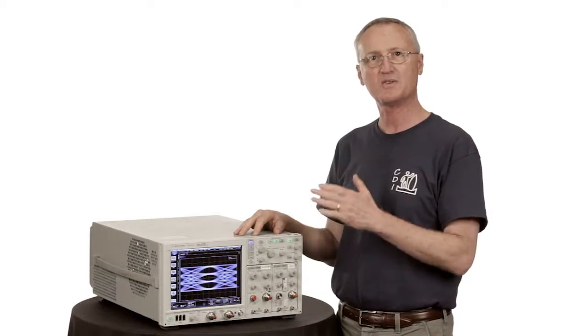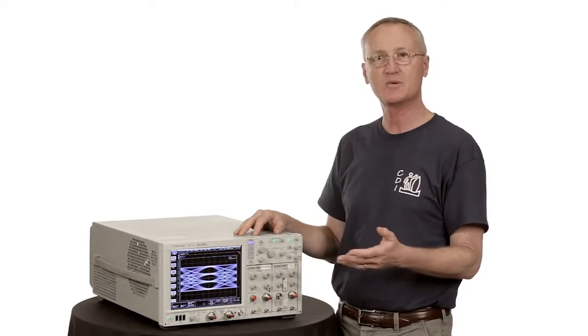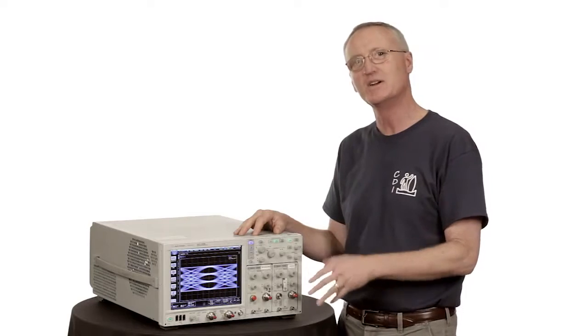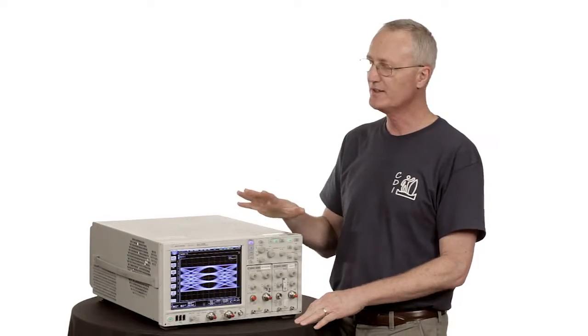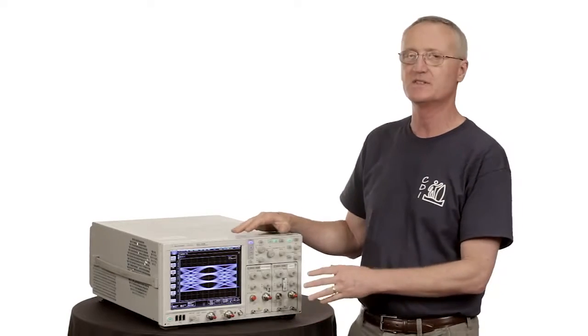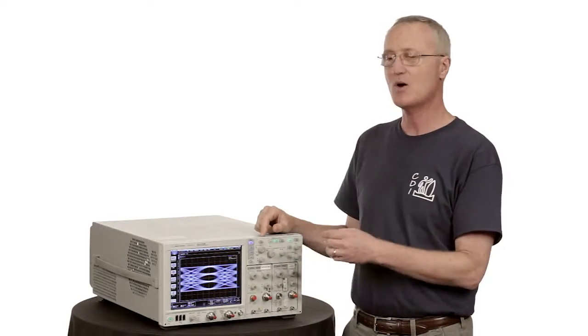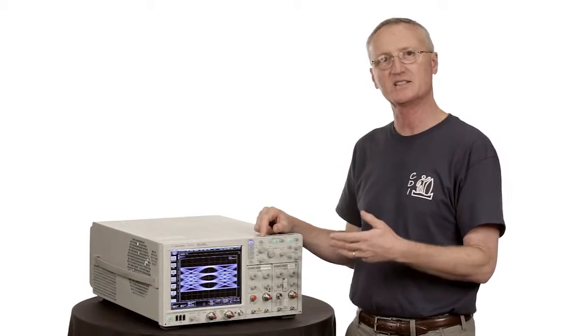It turns out not much. The hardware responds to edges. The edges come through in a PAM-4 signal similar to the way they did in an NRZ signal. Really, the only difference is that we have to tell the DCA not what the bit rate is, but in this case the baud rate.